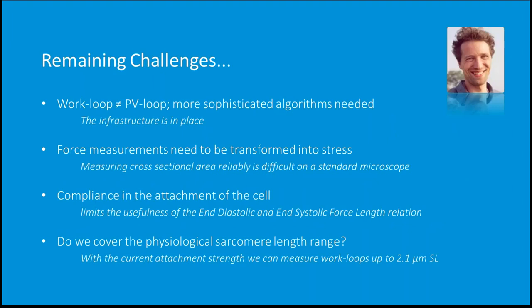I've talked about force. I've not talked about stress, which is probably something that you're very interested in. On the microscope that I have, measuring cross-sectional area reliably is pretty tricky. I can measure the width of the cell, but not the depth of the cell. So I have to estimate the cross-sectional area, and there's a fair bit of error in that. People on confocal microscopes don't have this problem because they could do a Z-stack, but it is a problem that needs to be solved for standard microscopes.